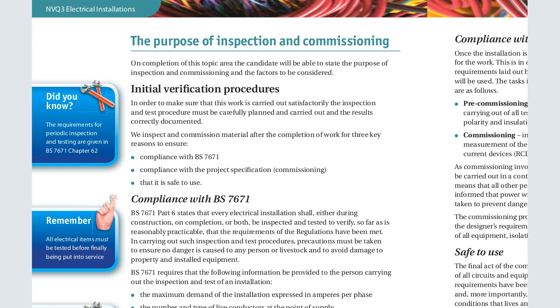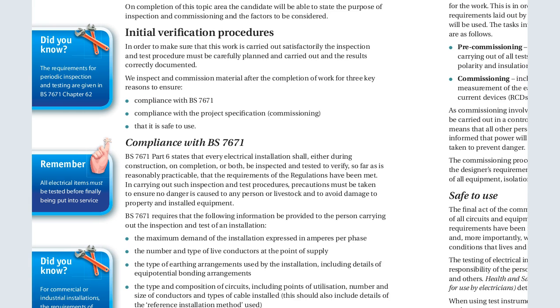We inspect and commission materials after the completion of works for three reasons. Number one, to ensure compliance with the BS standard, the British Standard. Remember, our country normally uses the British Standard, BS 7671. Then compliance with the project specification, that is commissioning, that it is safe to use. Part 6 states that every electrical installation shall either during construction, on completion, or both be inspected and tested to verify, so far as reasonably practicable, that the requirements of the regulations have been met.